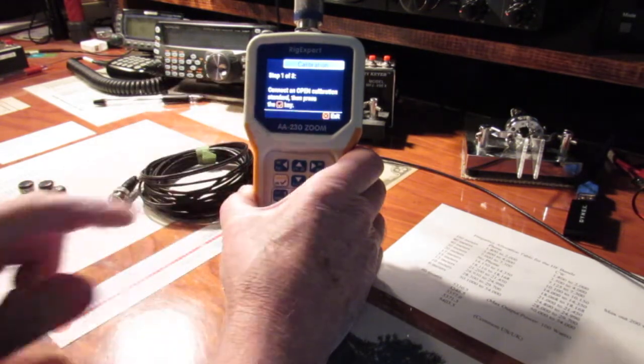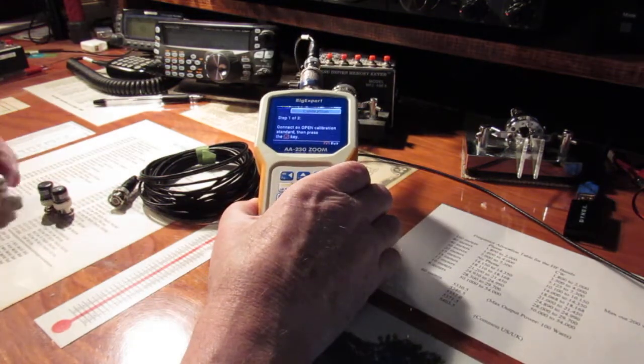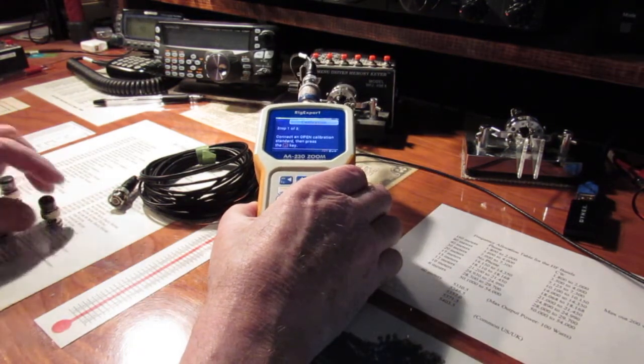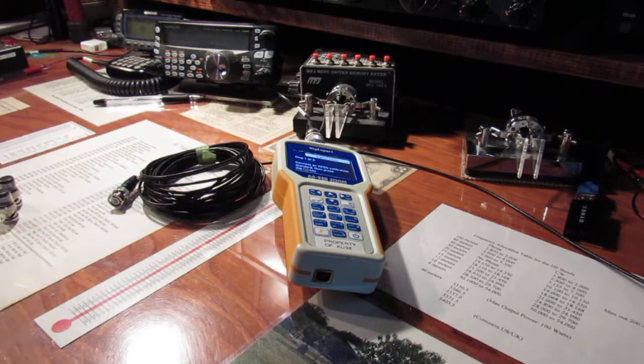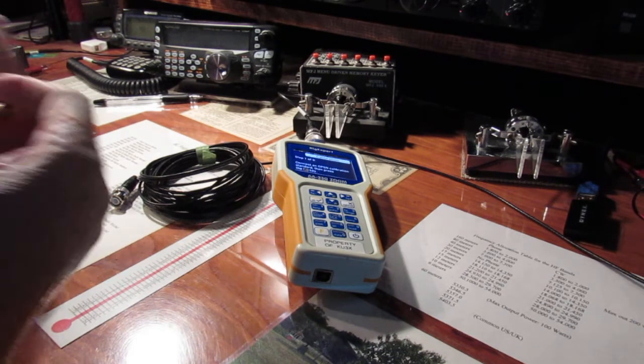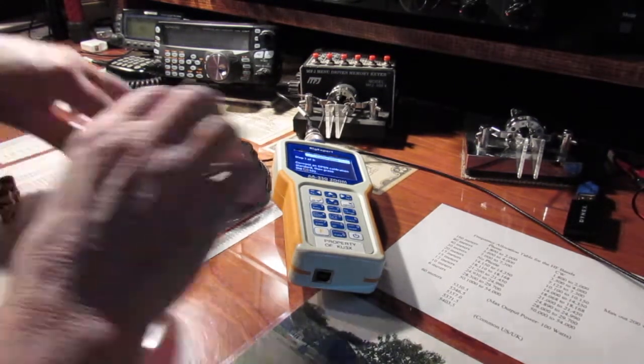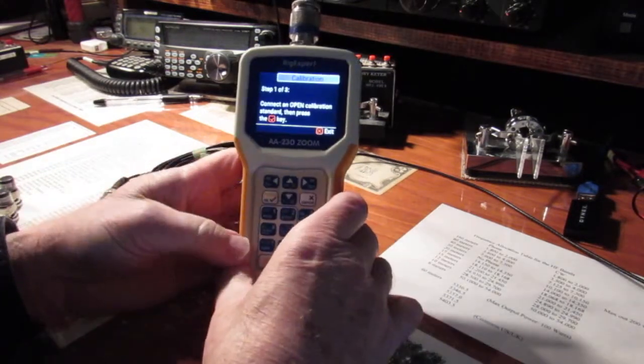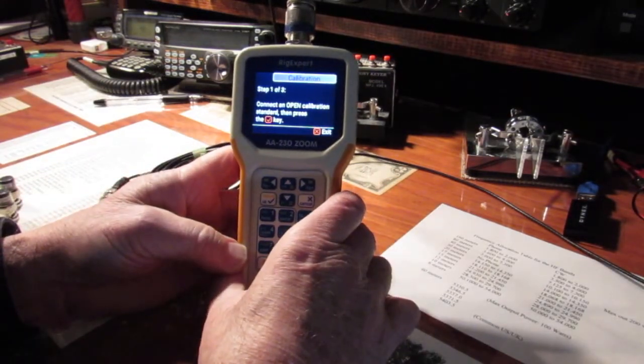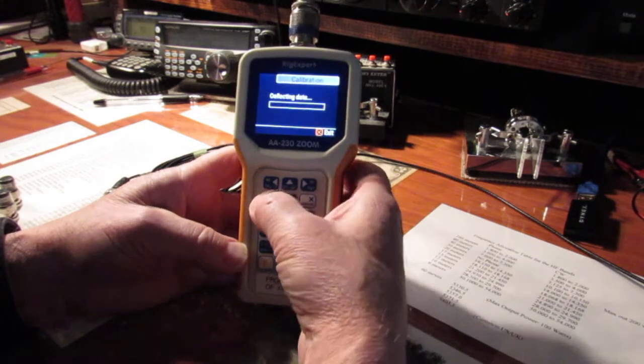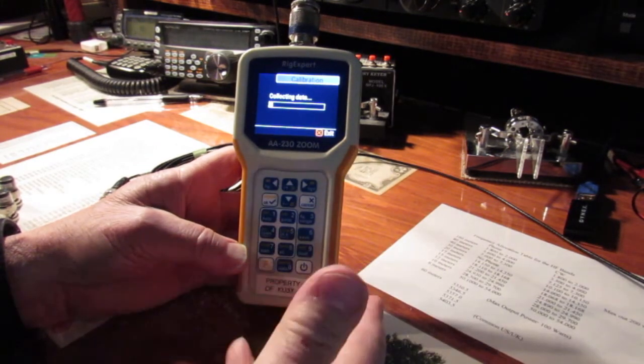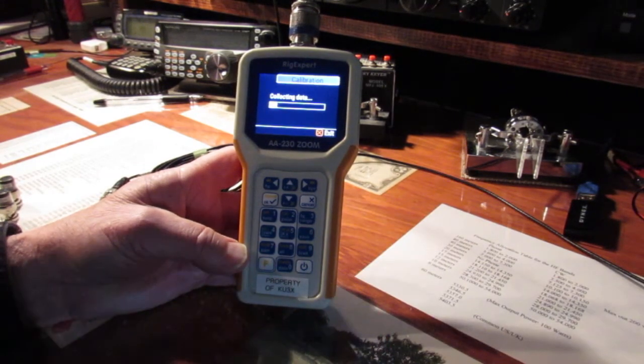Step 1, connect open. So we'll take one of these that are open, got to find it, and we're going to hook it to the other end of the coax. Just give me a second here, bear with me. Now remember, if you set those sampling points high, if it takes 20 minutes, I'm going to set this going. There we go. If you set this for 10,000, you're going to have to sweep every load.